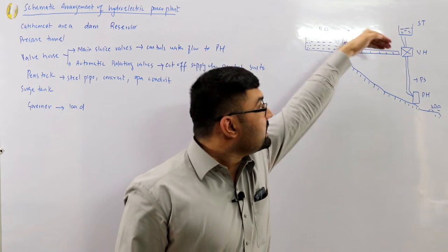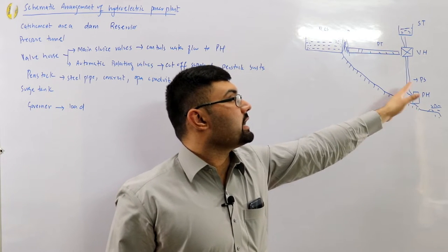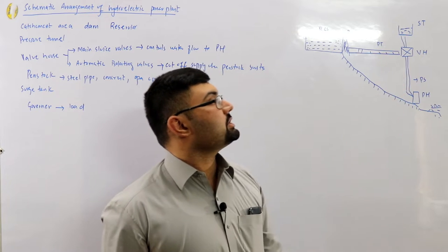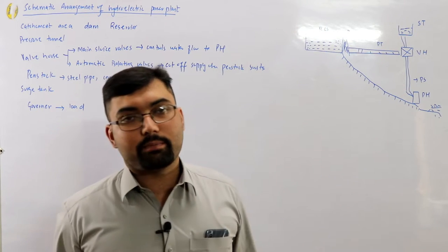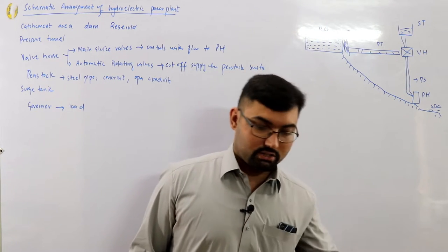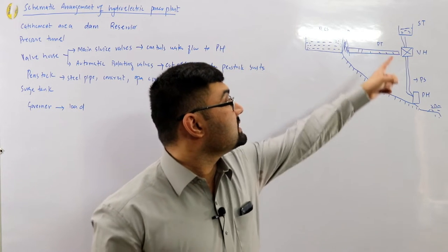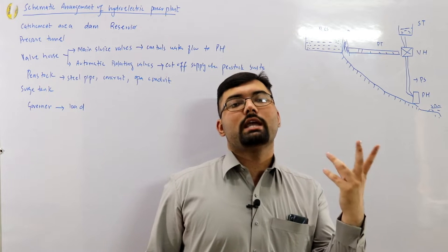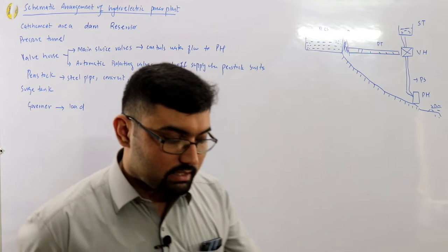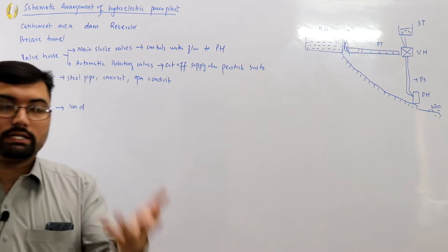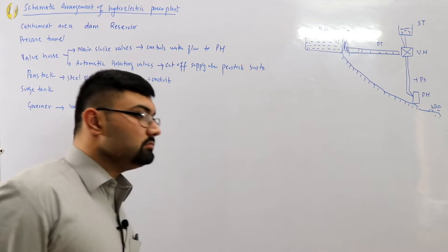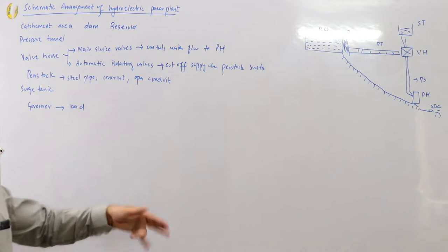the dam, is all present in the penstock, and it is not allowed to go any further. So the pressure has immensely increased in the penstock, and it could burst. So in that case, what happens is that the surge tank absorbs the abnormal pressure, and the extra water is taken by the surge tank, and the pressure is normalized. The opposite happens when the load increases.